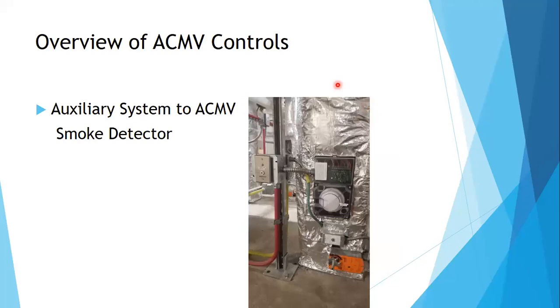Another one is smoke detectors. These smoke detectors are very important, especially in Singapore, where smoke detectors are required to be installed inside air handling units. So it acts like an early warning fire protection. When air is returned to the air handling unit, smoke detectors are installed to prevent the smoke from being transferred to other areas. So when the air handling unit senses that there's smoke, the air handling unit stops to prevent the smoke from spreading further.